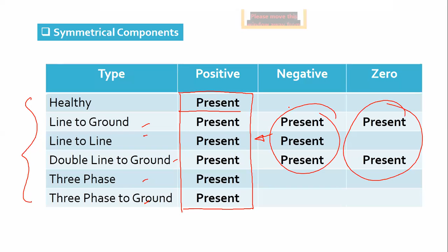So generally, if you design relaying applications, what is convenient is to design a relay which operates mainly on positive sequence components, because this is the component which is mainly present in all fault types. So generally relays are operated using the positive sequence quantities, except a few relays which may use the zero sequence, as well as some relays which may operate on negative sequence quantities. Fine.